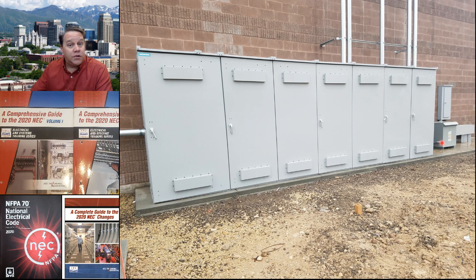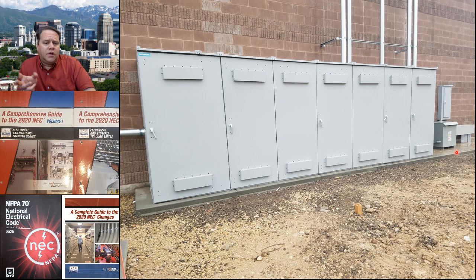Now, for the transformer, that is the supporting structure. So it's important that we get with our AHJ before we install this equipment, in fact before we pour the concrete, and ask the AHJ whether they think a transformer needs to comply with 110.26A3. Because some inspectors will say yes and others will say no, and the fact of the matter is it's up to them. This is an interpretive issue. So we want to find out for sure what the inspector expects, hopefully at the design stage, and worst case scenario before we pour the concrete.